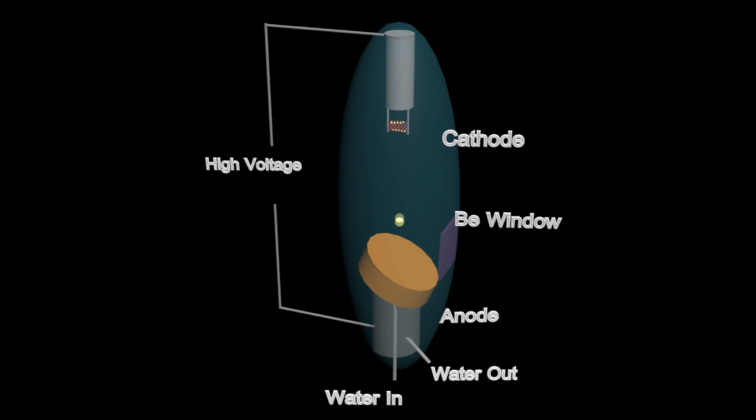The generated x-rays leave the tube through a beryllium window. This material is used because it has a low atomic number and therefore it doesn't absorb much of the x-rays.